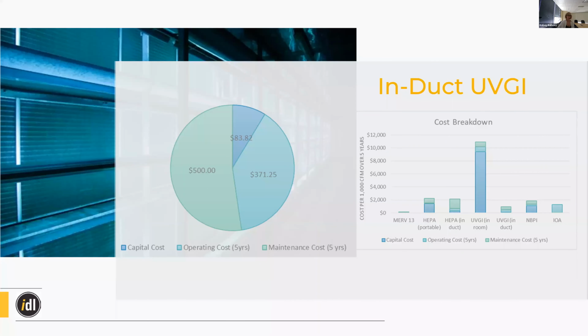So here's all of that a little bit more in depth. Pretty low cost, especially compared to what you'll see with the in-room UVGI systems. Really, it's capital costs. You just have to buy the lamps and install them. But the maintenance is the big one here, because you have to monitor them so carefully and make sure that the lamps are running at an efficiency where they're actually disinfecting the air or the coils. So maintenance associated with that is really the big one on this. But again, you don't have to clean your coils as much, so that's nice.